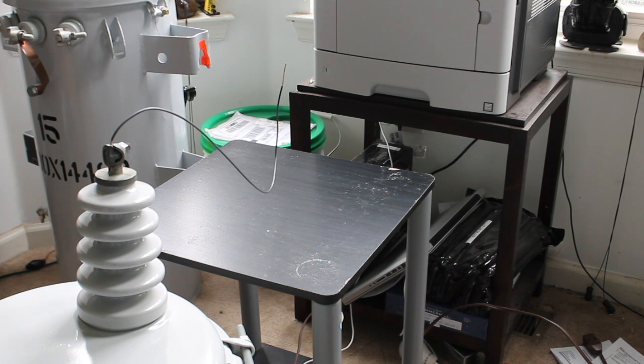My camera keeps cutting out while recording, but it pulled about 83 amps off the mains. That's because there was no ballast on it, which tripped the breaker immediately. So let me try this again.